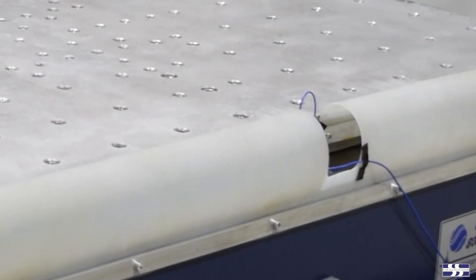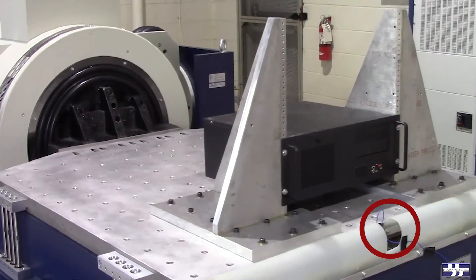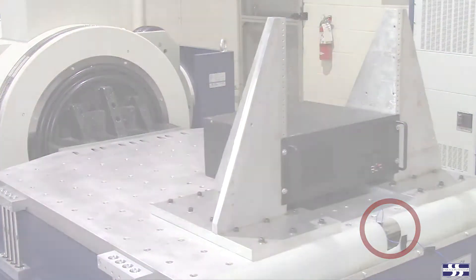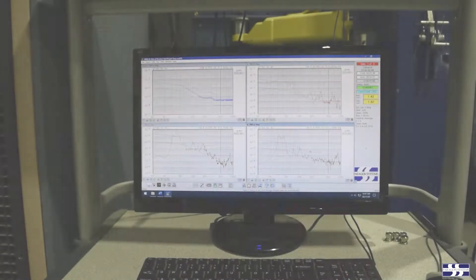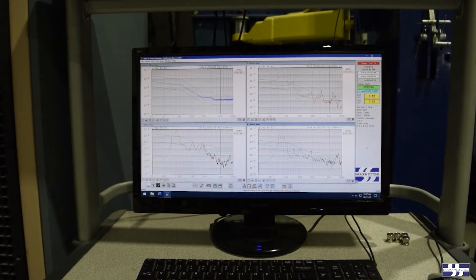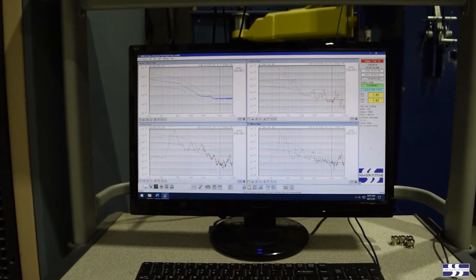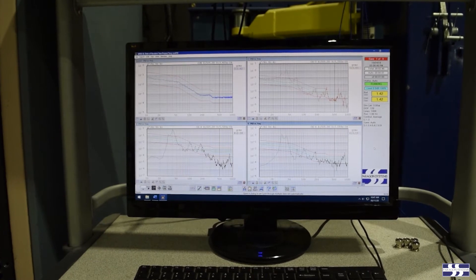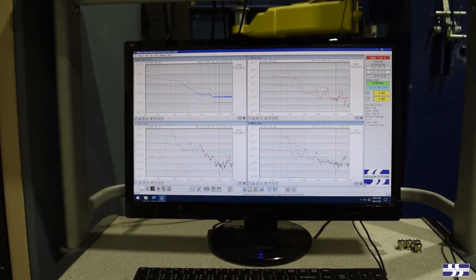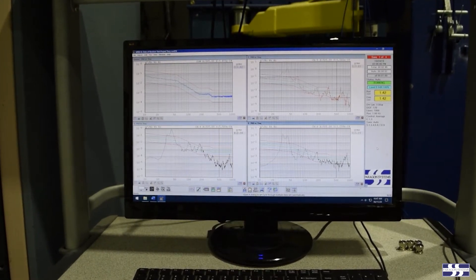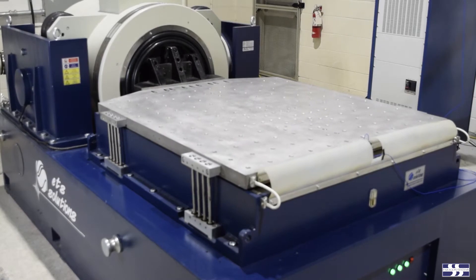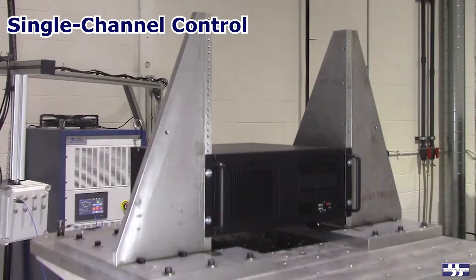Many vibration tests are controlled using a single accelerometer mounted to the shaker table surface. The vibration controller should have no trouble maintaining the test profile on the shaker table surface within the necessary tolerances. This type of control is called single-channel control.